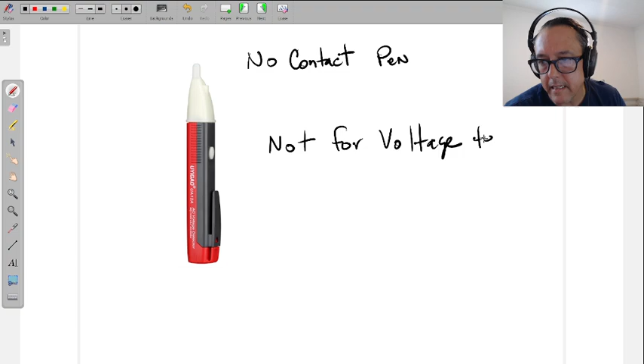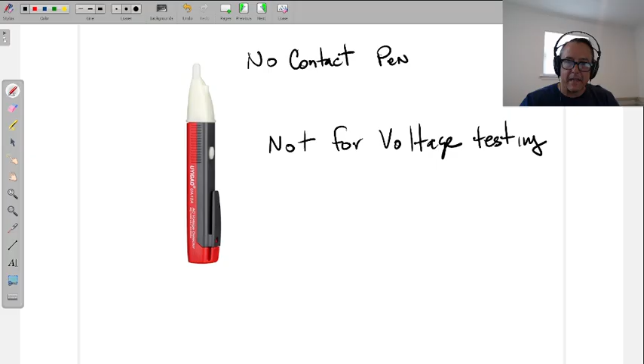And by the way, don't use this for an outlet. If someone says there's no power at my outlet, don't put it in there, because it could pick up magnetic fields on neutrals. It can pick up magnetic fields on any wire, so it's not for voltage testing, it only picks up the magnetic field. If I'm opening a junction box and want to know if there's a wire in here that's hot, then absolutely put it right there. Now I got hot in there, be careful.